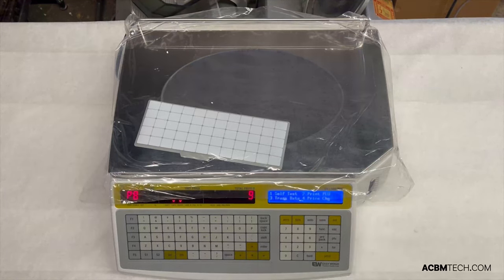After you've gotten to this screen, we want to focus on a self-test. This is going to do a diagnostic on the scale to figure out what's going on with these sensors for the label. Hit one and it's going to take us to the following screen.